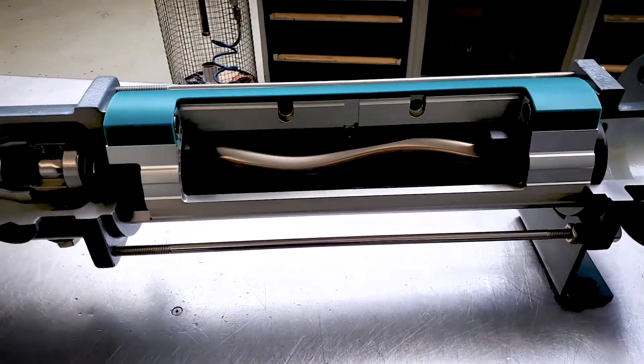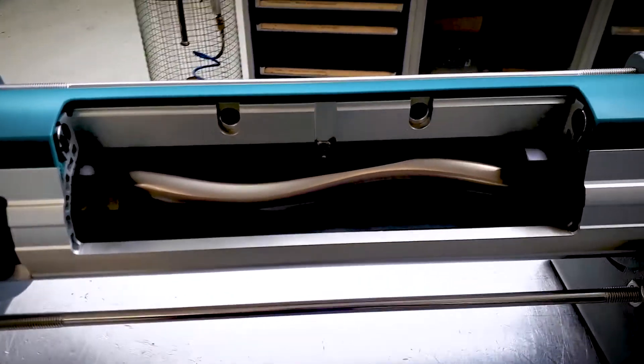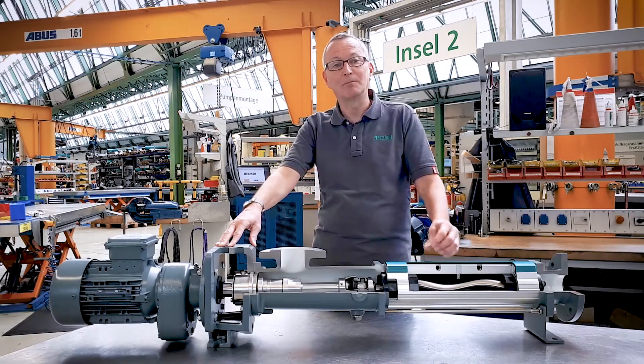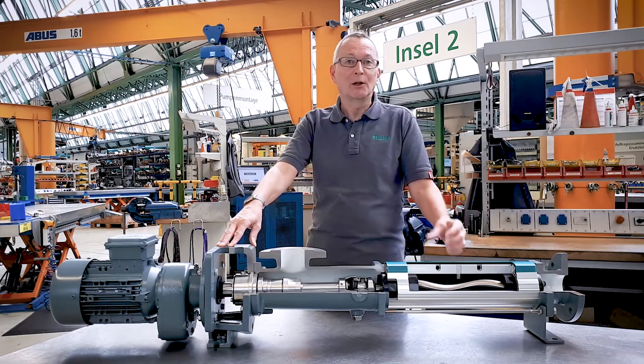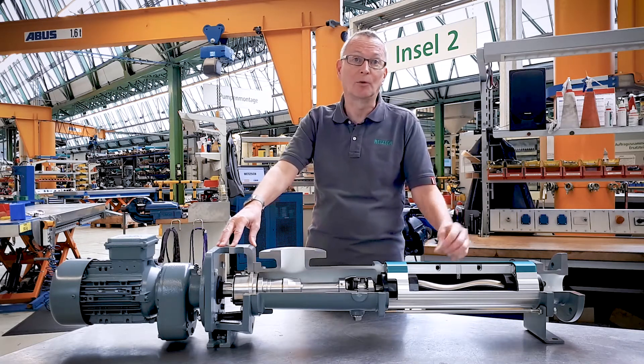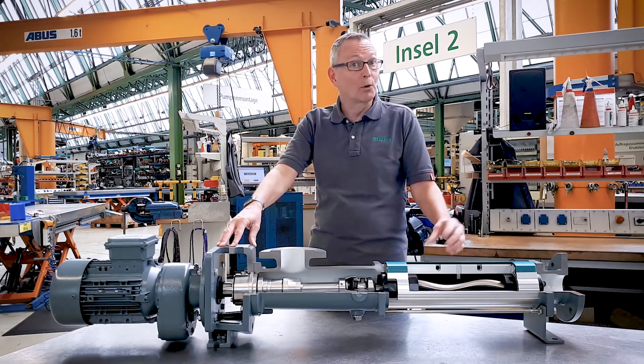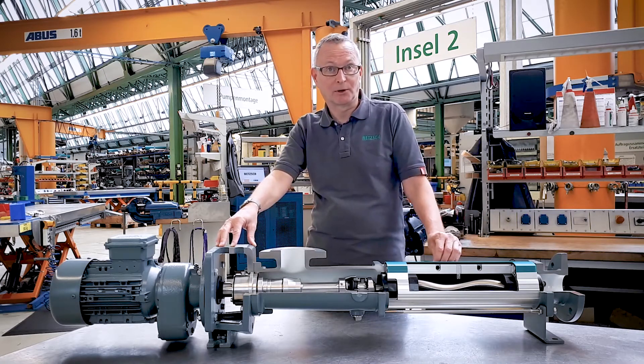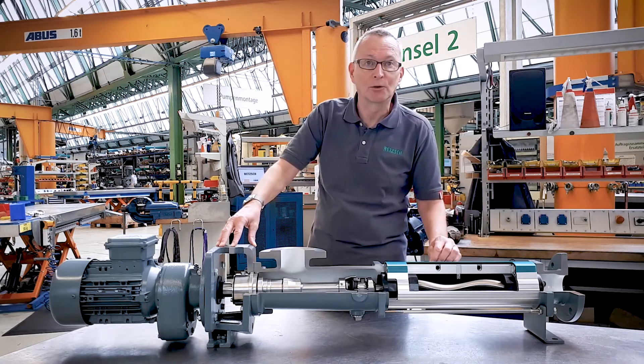Here you see a typical progressing cavity pump. A progressing cavity pump is used in applications where you may have a viscous product, an abrasive product, or a mineral slurry with high solids content. Additionally, the pump requires very low NPSH, meaning it can draw a column of water. The pump would also be used where you need to accurately dose a product — a typical example would be adhesives in the automotive industry.